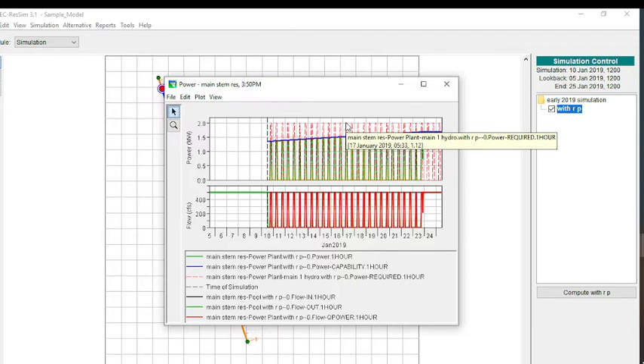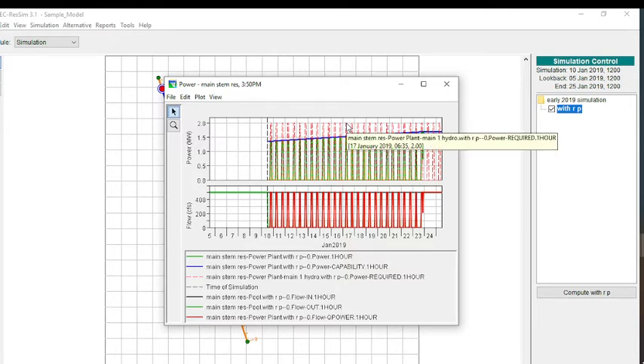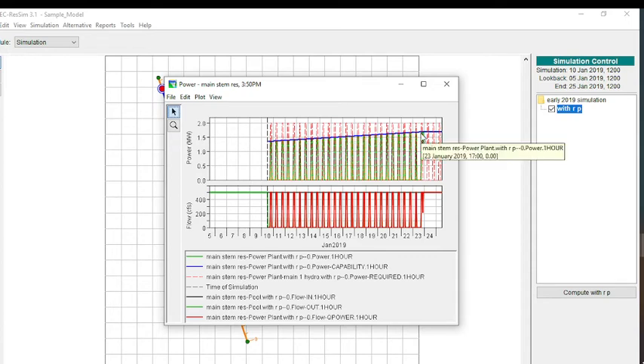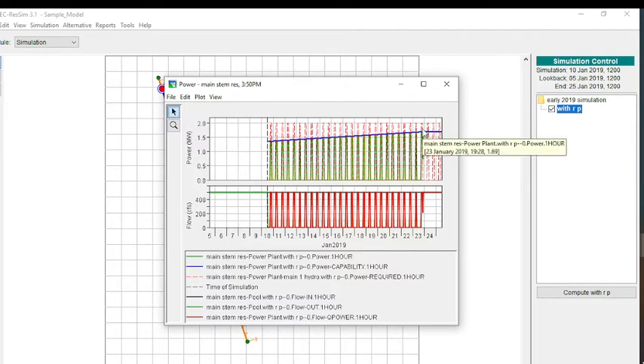This red dashed line is showing the required power or desired power of 2 megawatts, but we can't get 2 megawatts. We would need more flow or a higher pool elevation to create a higher head differential in order to get that 2 megawatts. The green is actually showing the power that is being generated. It does generate when we want it to generate up to the full capability because it's trying to get up to 2 megawatts. It just can't do it because of the parameters that we have.